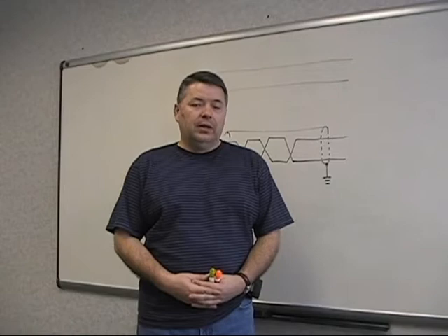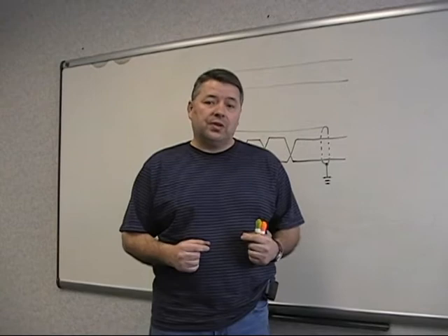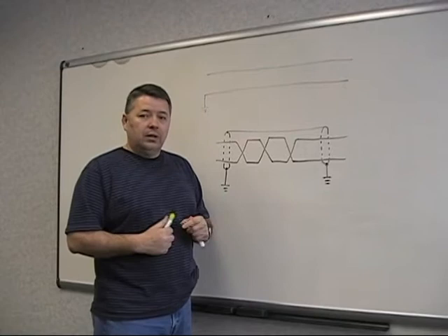The problem with an analog signal is it is very susceptible to electrical noise, as opposed to its digital counterpart. But there are a couple of steps we can take to reduce the effects of noise in our system. The first is to use shielded twisted pair cable, making sure that the shield is tied to ground at both ends. The second is to use a differential input.